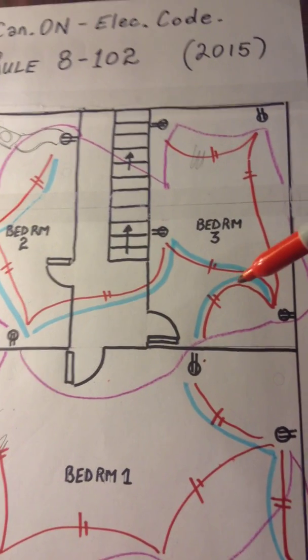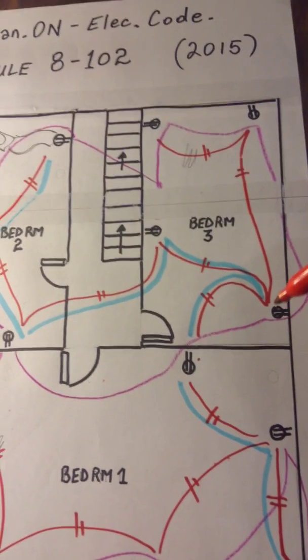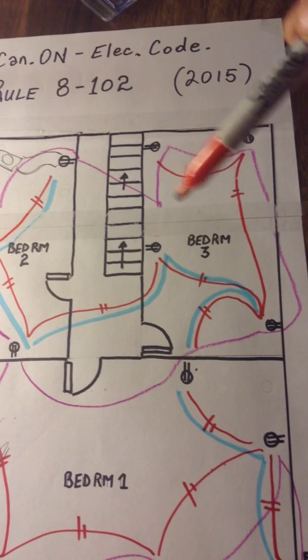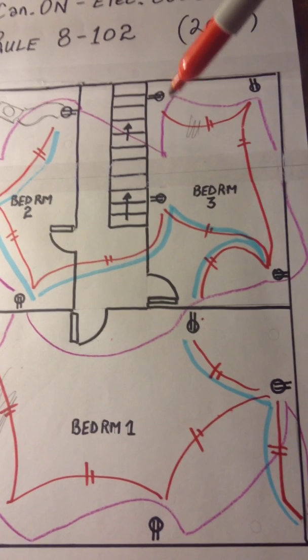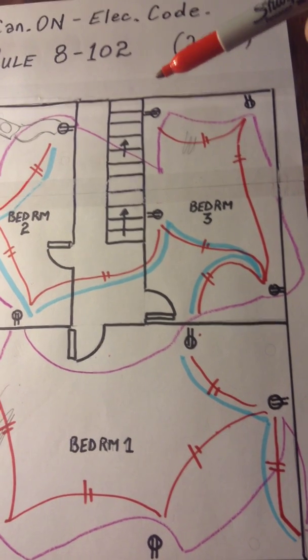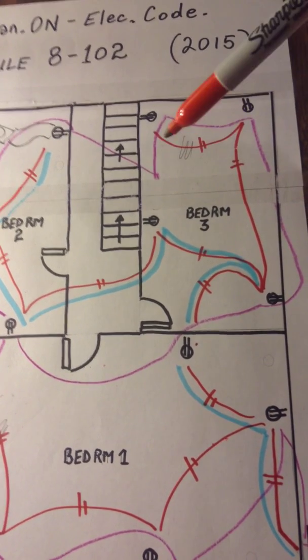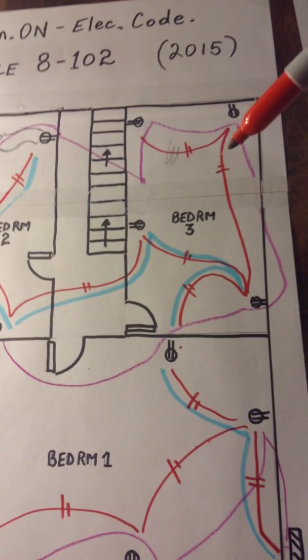Let me get my red marker. How I would wire this - you want to be strategic. As I mentioned in this diagram, you want to be strategic with breaking the wire and stemming off into different little zones. Those little zones will not account into the distance of the voltage drop as long as it doesn't exceed 125 feet. When you stem off into little zones, you stay safe, keep it short, and it's good for resistivity.